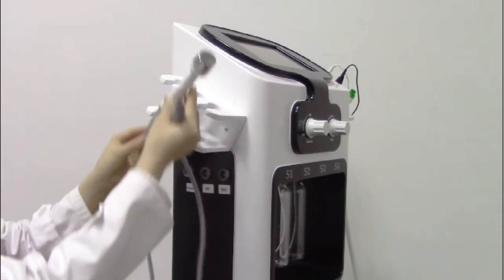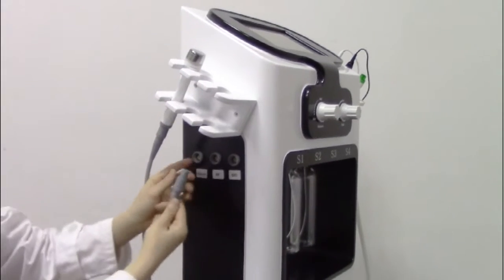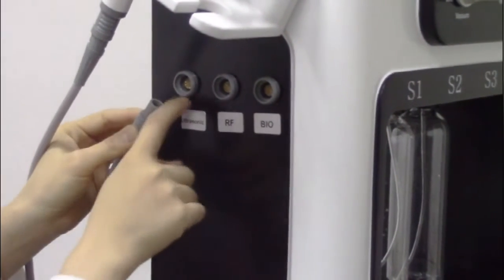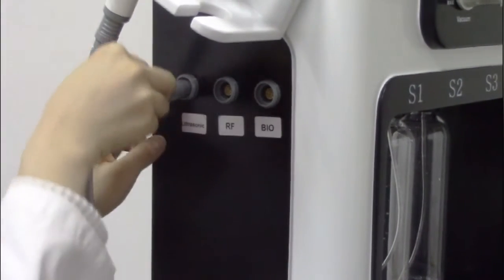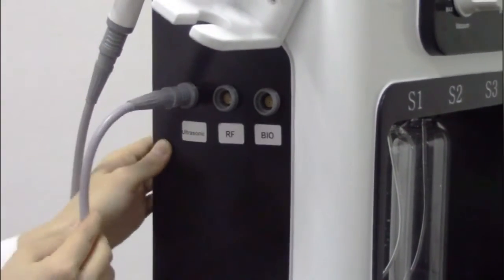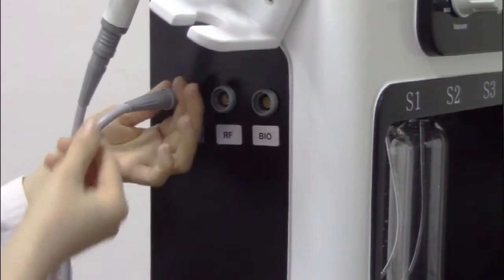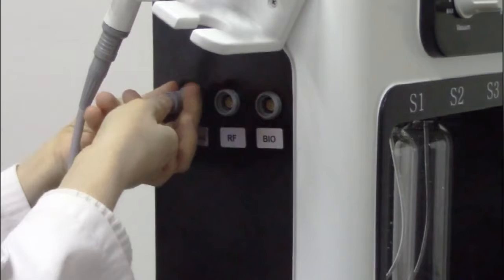Now we introduce the Ultrasonic handle piece of the machine. You have to make sure that these two lines match these two lines, and then insert directly. When you want to take out the handle piece, you have to push the disc with one hand and take it out.